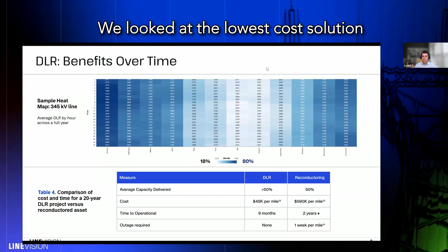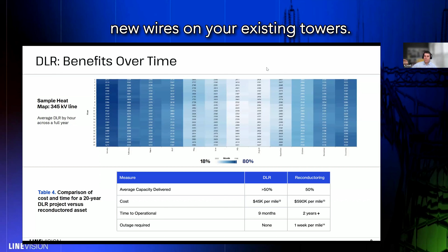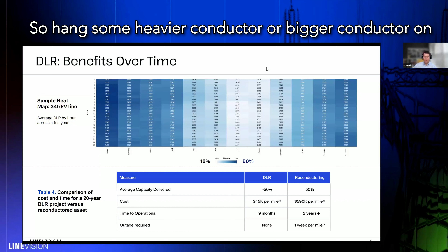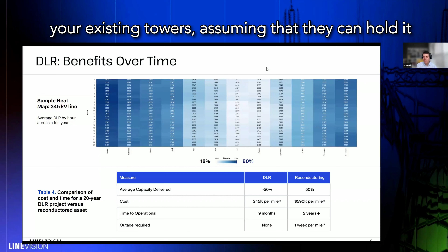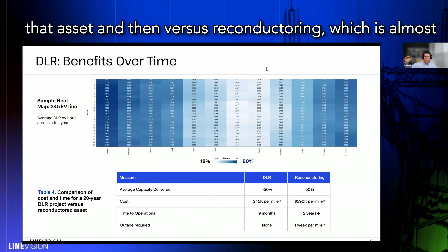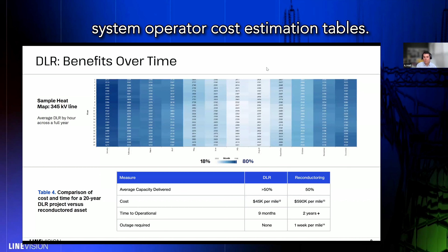We looked at the lowest cost solution to increase transmission capacity, which is to string new wires on your existing towers. So hang some heavier or bigger conductor on your existing towers, assuming that they can hold it. This is where DLR is less than 8% of the cost. It's roughly $45,000 per mile when you take into account installing DLR and then a 20-year software cost for the life of that asset, versus reconductoring, which is almost $600,000 per mile based on MISO, or Mid-continent System Operator, cost estimation tables. And really importantly here, the time to be operational.